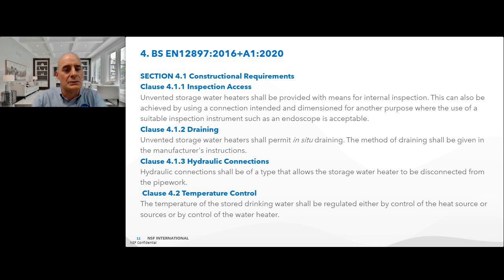Clause 4.1.2, draining. So unvented storage water heaters should permit in situ draining. The method of draining should be given in the manufacturer's instructions. Clause 4.1.3, hydraulic connections. So hydraulic connections should be of a type that allows the storage water heater to be disconnected from the pipework. Normal arrangements are compression fittings, threaded connections.